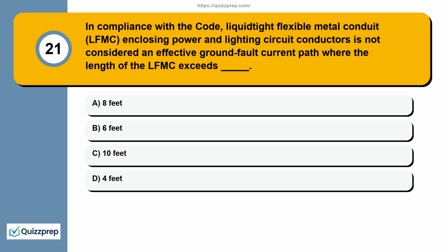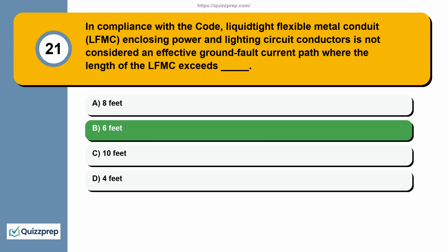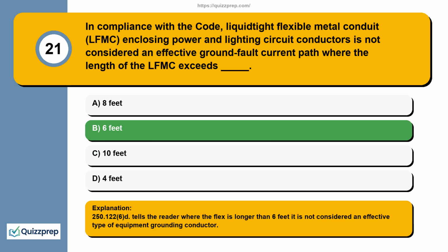Question 21. In compliance with the code, liquid-tight flexible metal conduit, LFMC, enclosing power and lighting circuit conductors is not considered an effective ground fault current path where the length of the LFMC exceeds 8 feet, 6 feet, 10 feet, 4 feet. 250.122(6)(d) tells the reader where the flex is longer than 6 feet it is not considered an effective type of equipment grounding conductor.